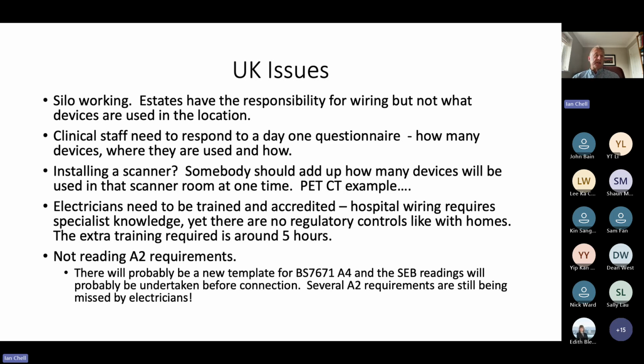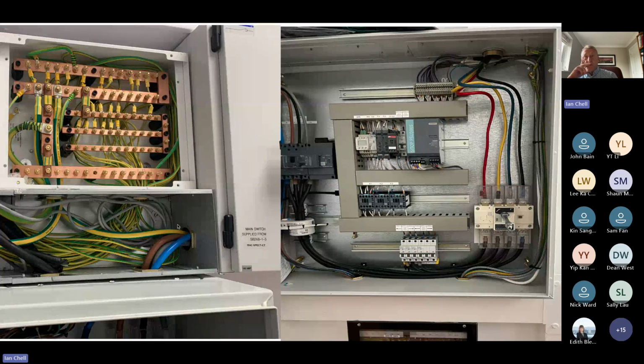Another big one is that electricians are not doing this. They certainly are not reading the Amendment 2 requirements of 7671. Okay. I've got some examples in a second, but again, I can only repeat what is going on, and something needs to be done about it. These are two recent examples from hospitals. On the right-hand side is a contactor box for an x-ray room. Excuse me.